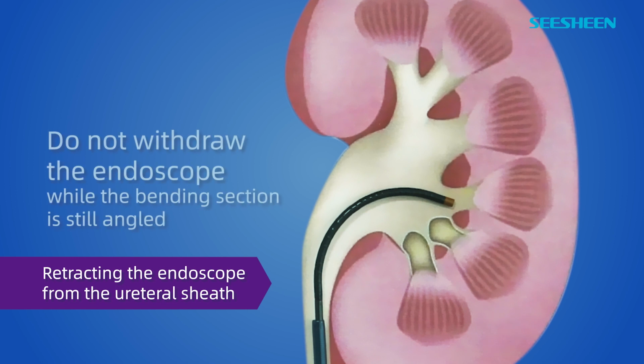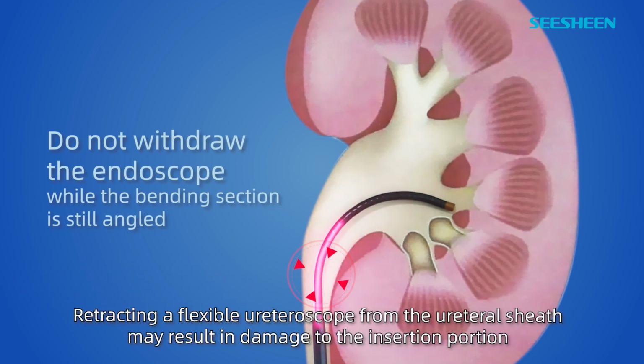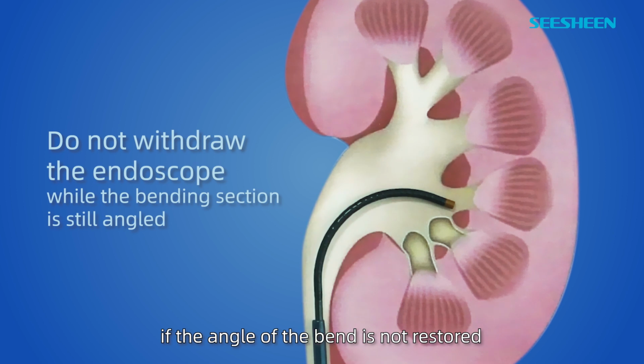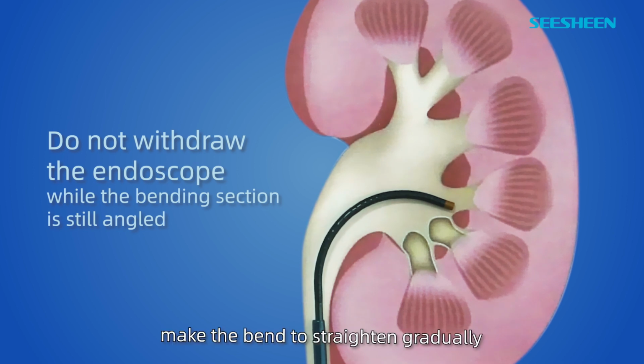Do not withdraw the endoscope while the bending section is still angled. Retracting a flexible ureteroscope from the ureteral sheath may result in damage to the insertion portion if the angle of the bend is not restored. Make the bend straighten gradually.